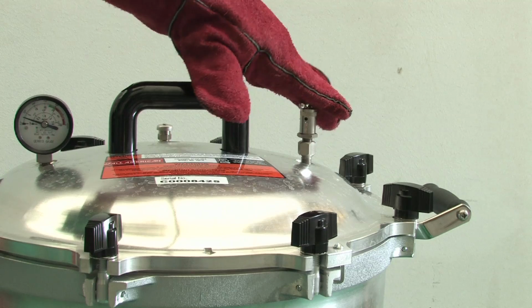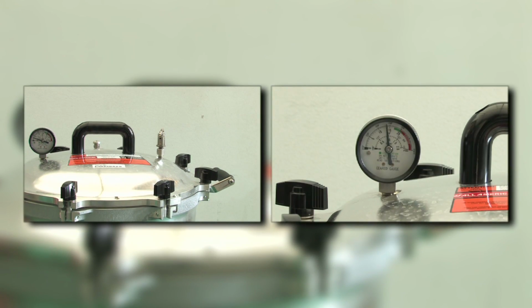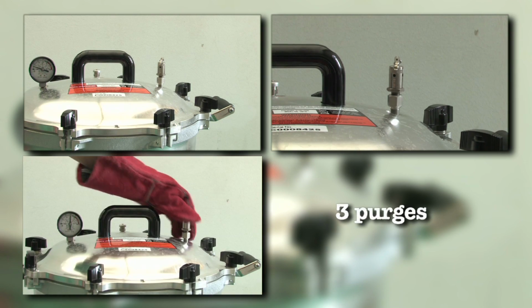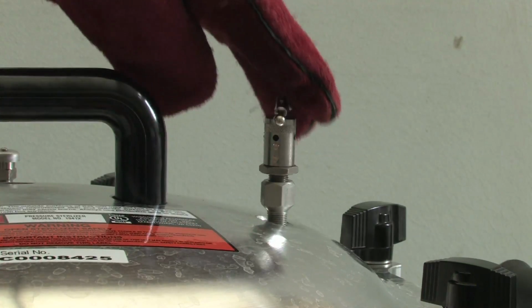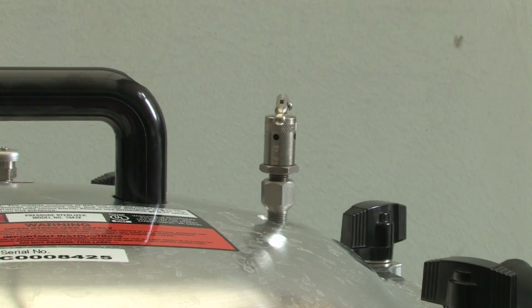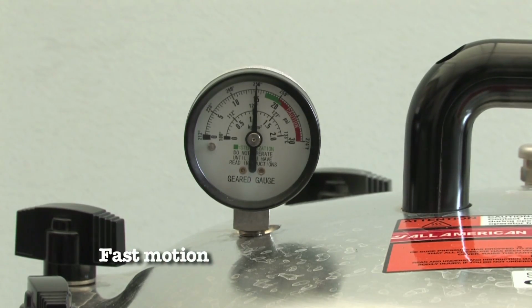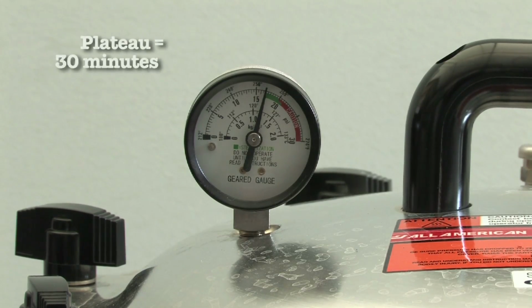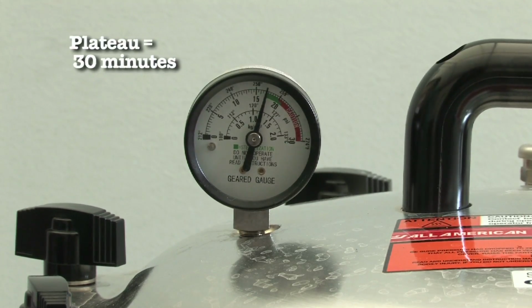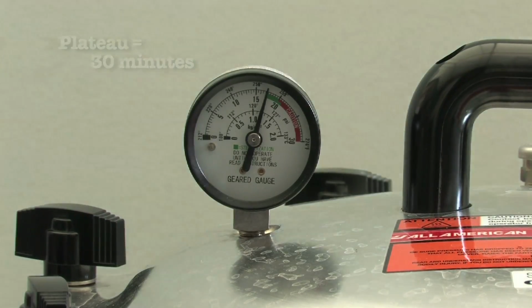Then close the valve. 9. Repeat this operation twice more, for a total of 3 purges, to remove all of the air in the autoclave. 10. Sterilization. After 3 purges, begin timing the 30-minute sterilization plateau as soon as the pressure reaches the green zone. That is, a pressure greater than 1 bar and less than 1.4 bars.